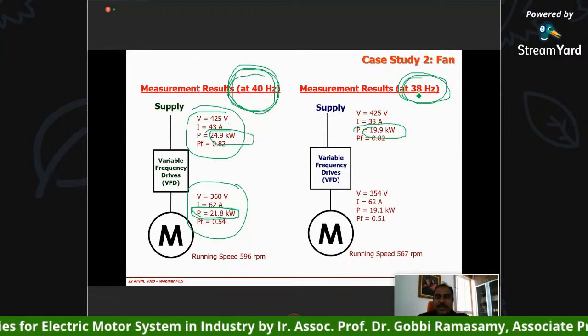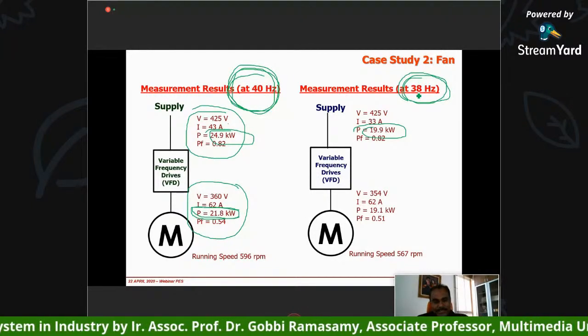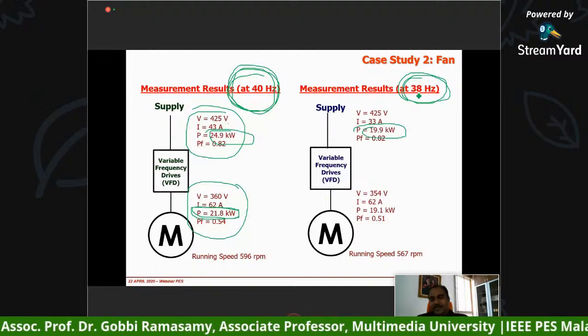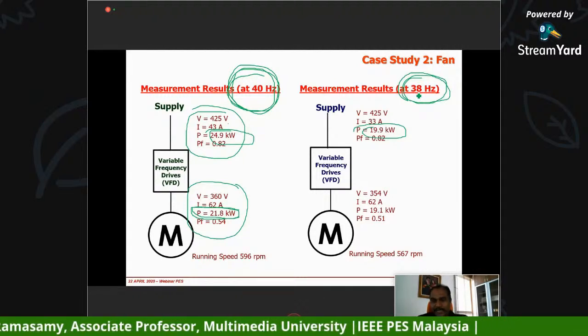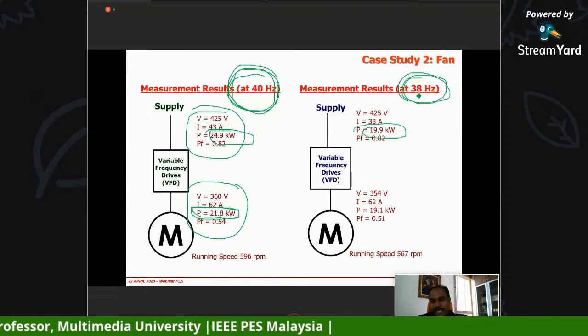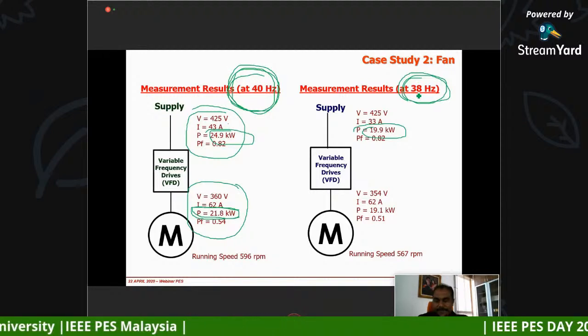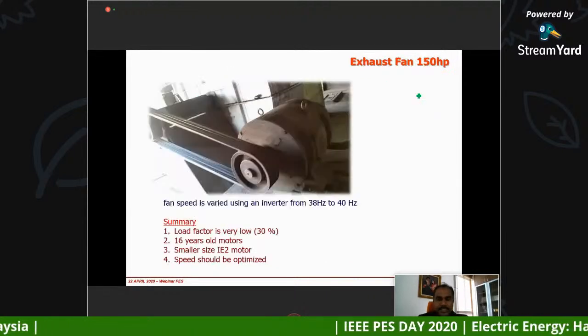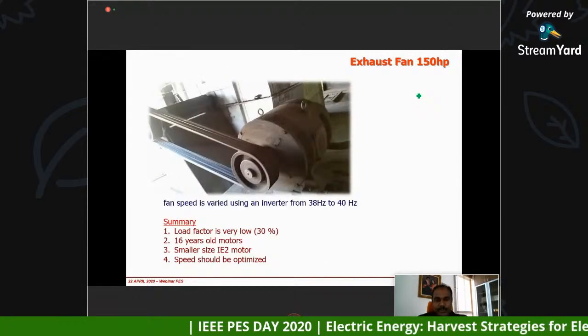Number two, the motor is completely oversized. If you can reduce the size of the motor, probably you can have better efficiency. You can further reduce the kilowatt in this case. All right? So this is the exhaust fan that I mentioned just now to you.